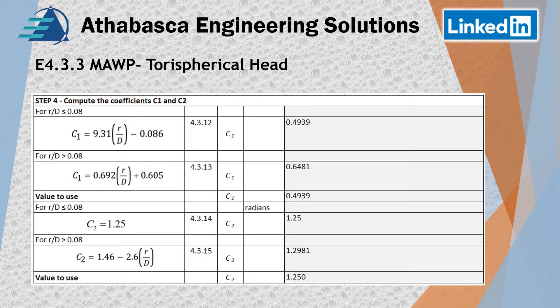In step four we continue our calculations, looking at the R over D ratio — that's why we did those setups before. If R/D is less than or equal to 0.08, we calculate one factor; with the other condition where it's greater, we use the 0.439 value. Then we continue on calculating C2 — a very similar procedure. The equations are not too bad, and we've referenced the equations from the 2019 edition. We calculate the C1 and C2 values in step four.